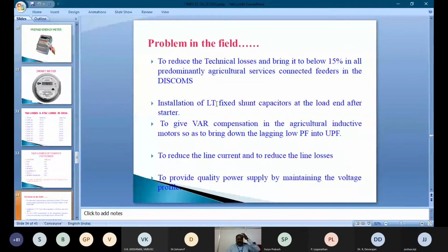So, the problem in the field. What is the problem in the field? Here, we need to reduce the technical losses and bring them below 15% in all predominantly agriculture service connected feeders in the DISCOM. In agriculture services, once we give the service, the consumer enjoys the power free of cost. So he need not bother about the efficiency of the motor. Even a good old motor draws more current, and the I square R loss is also more. So he doesn't bother about the losses, but the utility makes huge transmission and distribution losses. So we have to bring them down.